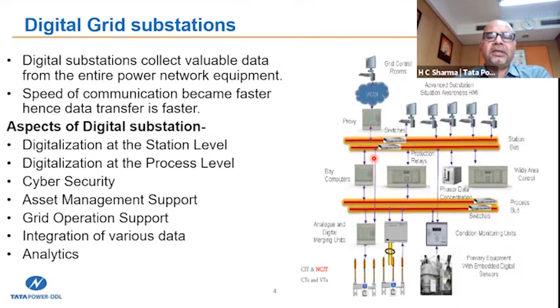The advantage of this type of substation is that it is very safe, low energy, and the signals are transferred through fiber optic cables. You don't have to run a bunch of copper cables. It takes a lot of time, and then if there is any fault in the cables, it becomes very difficult to find out where the fault is. So the number of wires running from the substation building to the field equipment becomes very low. It is like earlier instruments, like the earlier pneumatic system, where all the tubes used to run to the control room. And as of today, digital electronic signals are coming from field equipment to the control room.